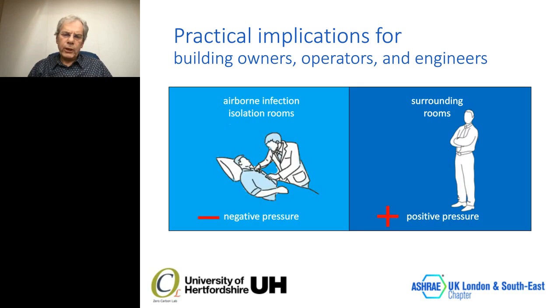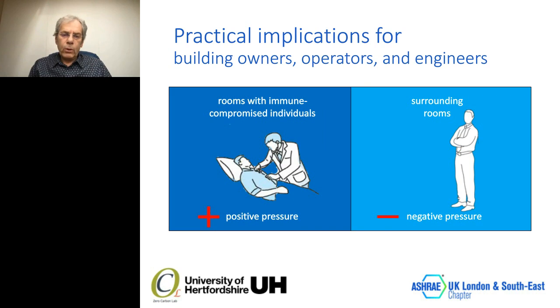So basically, on the left of this slide, you have an airborne infection isolation room. We put it on a slightly negative pressure, only a few pascals difference between that and the surrounding rooms. And infection is not going to go out. Airborne particles are not going to go out. But if we want to protect people with immune compromised systems, we put such rooms on a slightly positive pressure, just several pascals, and keep surrounding rooms at negative pressure.